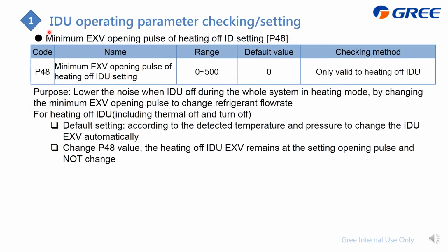Indoor unit operating parameter checking and setting. First is P48. This is the minimum EXV opening of the heating-off indoor unit. First of all, what is a heating-off indoor unit? That means an indoor unit that is thermal off, where the room temperature meets the set point and this indoor unit turns off, right? This is the heating off, and it also includes when you turn off the indoor unit manually.